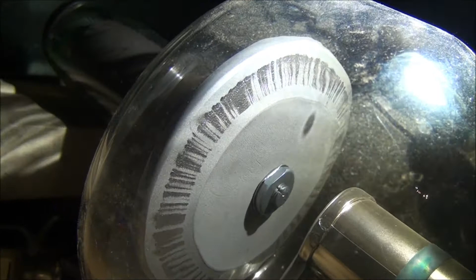Otherwise you wouldn't see those burn-in scars on the face of the tube there. Yeah, some are quite heavy, and so I'd say that the tube wasn't rotating very fast at all when exposures are taking place. Otherwise it should spread the heat out much more evenly across that face there, because you basically will melt the target down with overexposure.